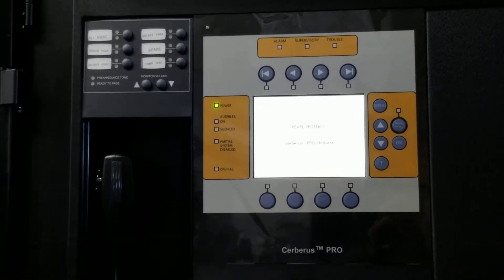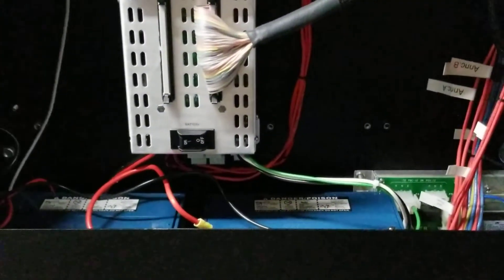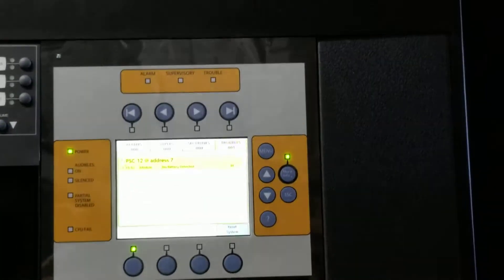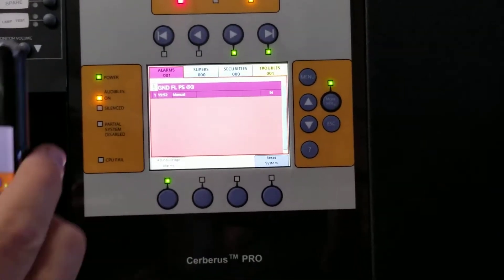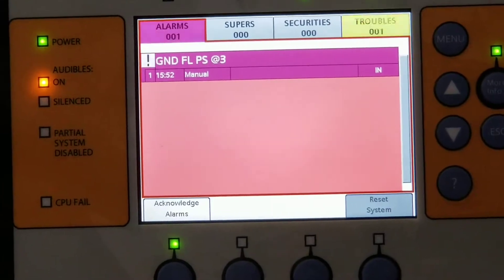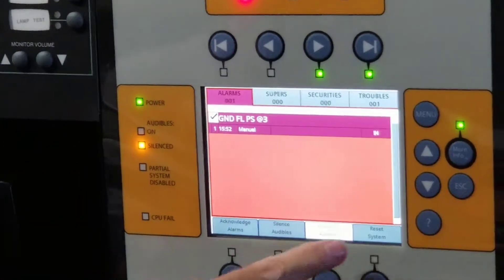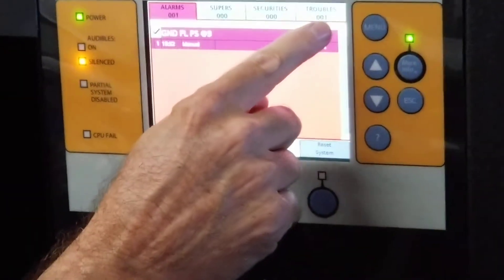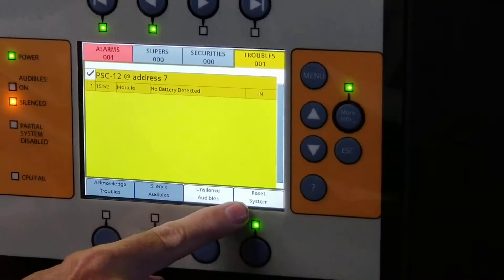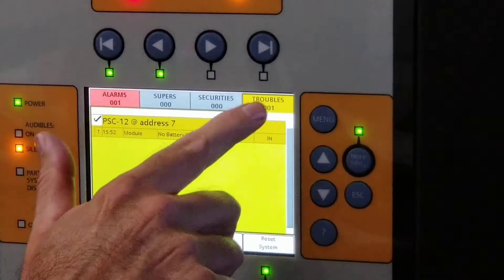You have to hit trouble to go back and acknowledge it. He had just turned off the main power to give it a trouble, and then pulled the pull station. So the pull station popped in. We're back to fire — hit acknowledge, then silence. How come I can't hit reset? You have to go to trouble — it's trouble up here. Then acknowledge trouble, then it shows the reset button. Everything has to be acknowledged.